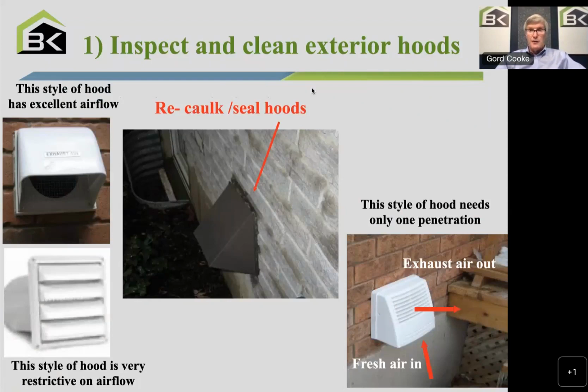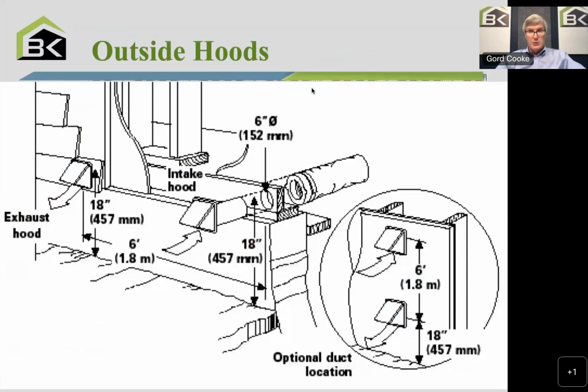So that's the first thing to think about. You're using a stiff brush, maybe a rag. Don't really need to wash them or anything. Just brush them off to make sure they're clean and clear. So that's number one. And just a reminder of where those hoods typically are. If you're outside, you're looking. Sometimes as trees or bushes build up, you don't see them.